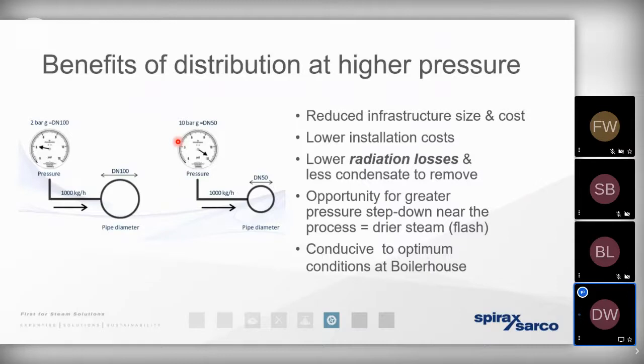So, of course, there's going to be a significant cost saving on the infrastructure there, but there's another cost that is often overlooked. If we've increased the working pressure of the steam, increased the distribution pressure, reduced its volume, and therefore reduced the infrastructure size, we've also reduced the space or the area that the steam can give up its heat energy and condense against. So that means we're reducing the radiation loss. We've got less condensate to remove, so we've got a greater efficiency with fewer steam traps to install. And the steam is going to be far, far drier, meaning we've got fewer mechanical issues and there's more heat energy present in the steam to satisfy the process.